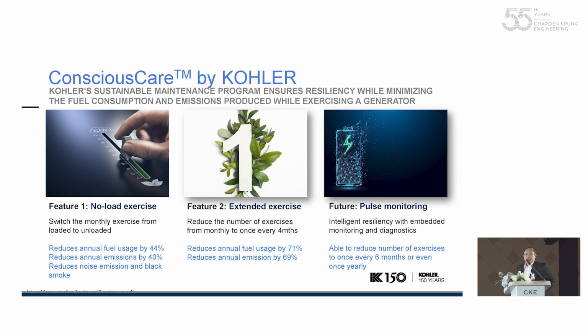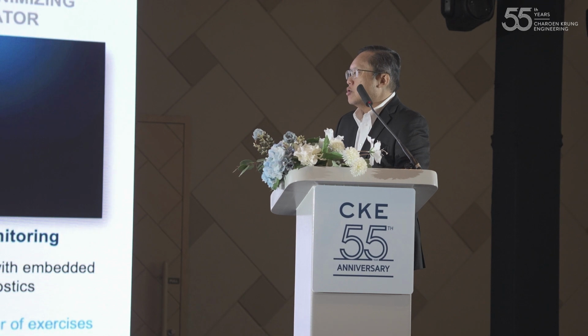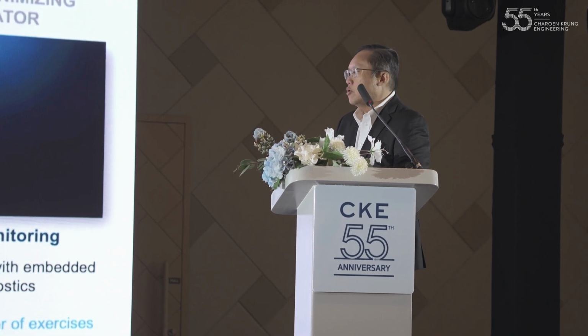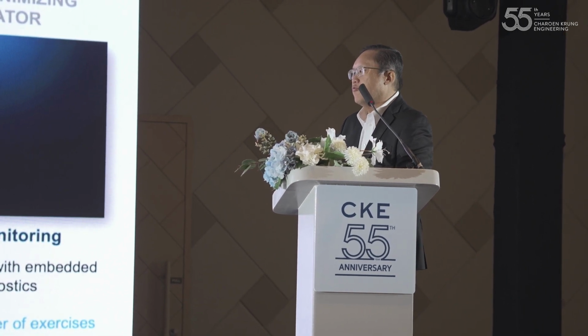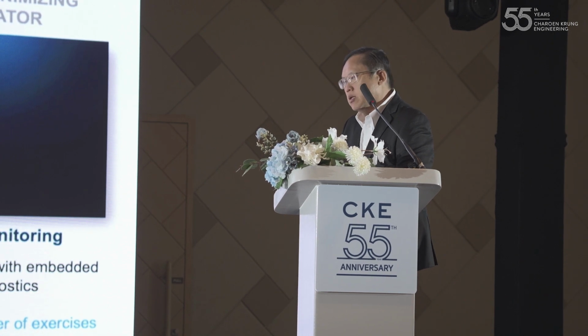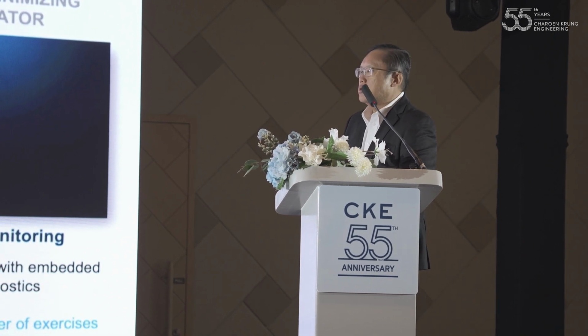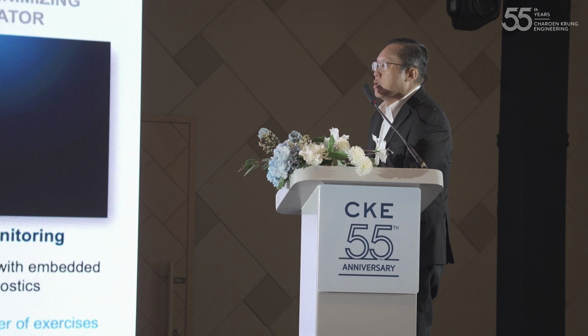You can do your monthly exercise at zero load, meaning you don't apply any load at all. Most manufacturers require a minimum load of 30 to 50%, but Kohler can offer zero load. This reduces fuel consumption by 44% and annual emissions by up to 40%.